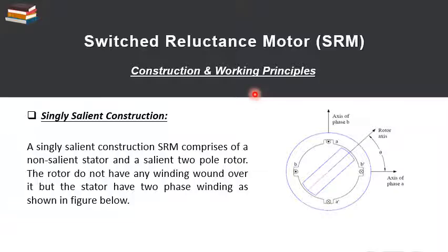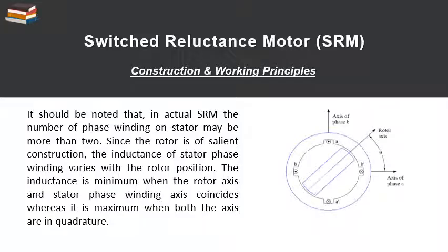In the singly salient construction, the rotor does not have any winding on it, but the stator has two-phase winding as shown in the figure. It should be noted that in the actual switched reluctance motor, the number of phase windings on the stator may be more than two. Since the rotor is of salient construction, the inductance of the stator phase winding varies with the rotor position.